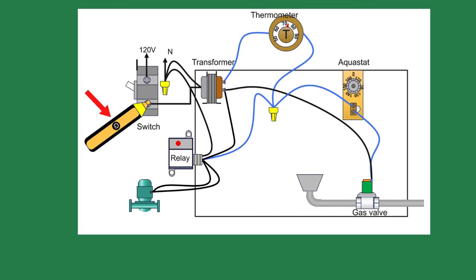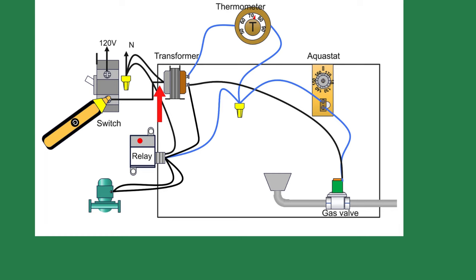The next step is to verify there's voltage to the boiler. You can do that either using a non-contact voltage detector or your meter. Be sure the boiler is getting 120 volts. If not, look for the breaker or another switch that's off. If you have power to the switch outlet screw, we know there is power to the primary side of the transformer.